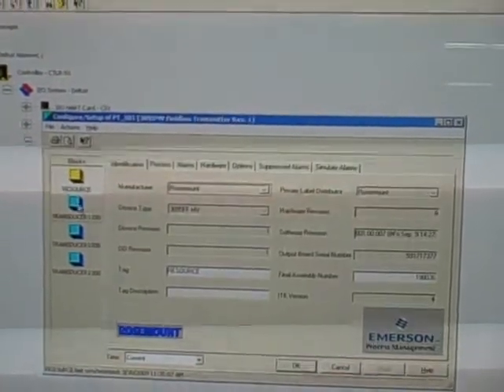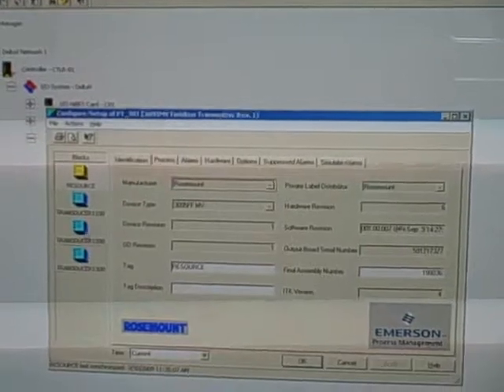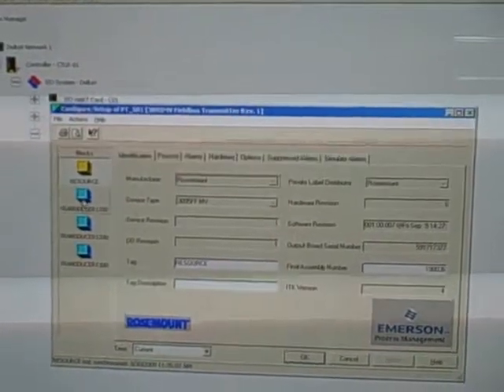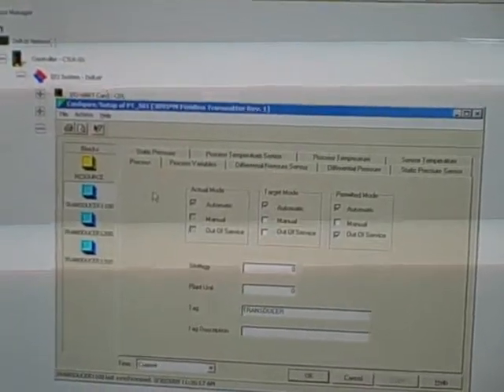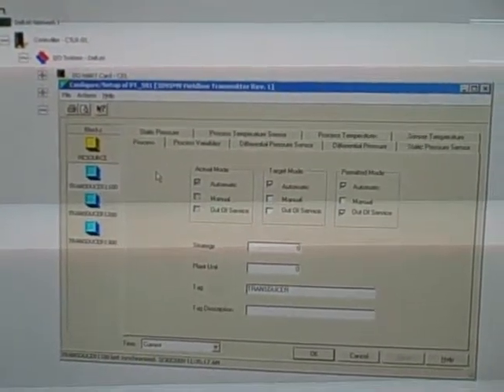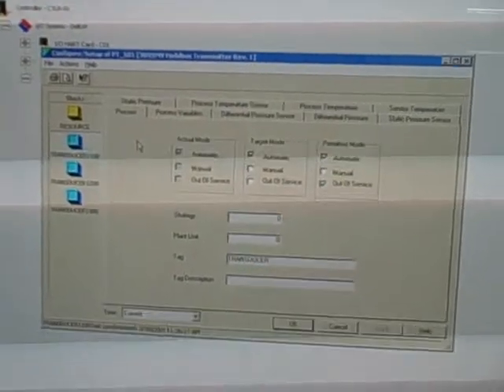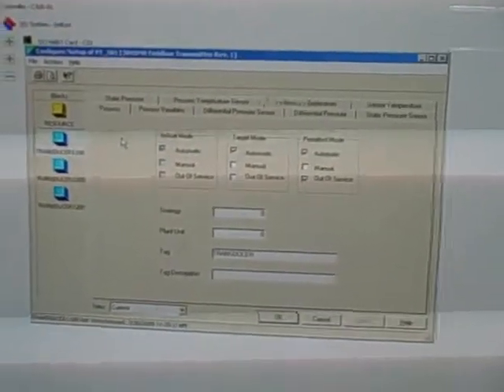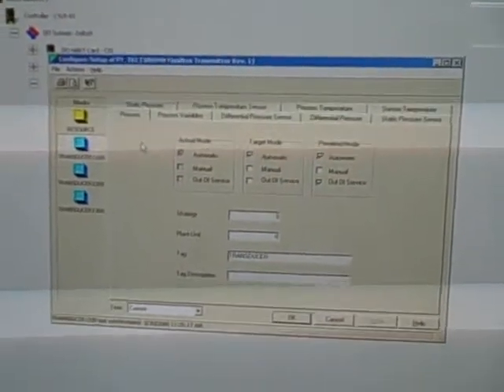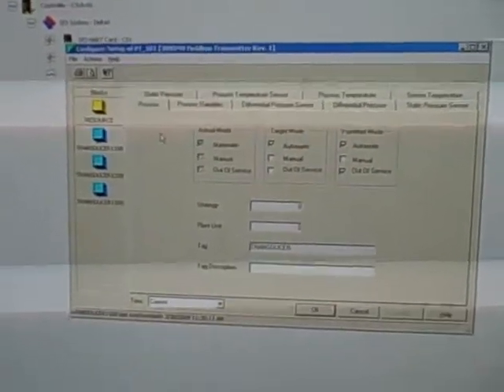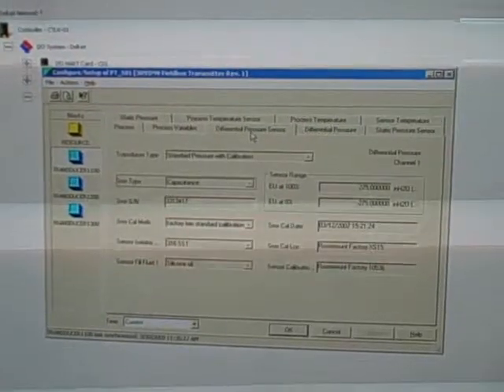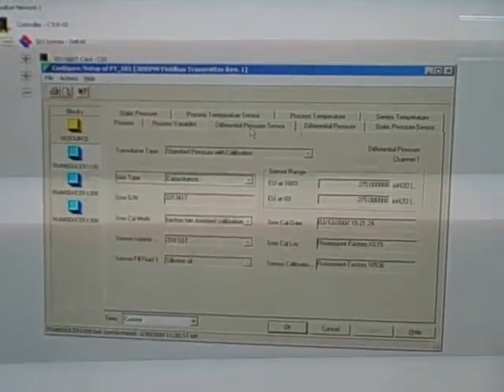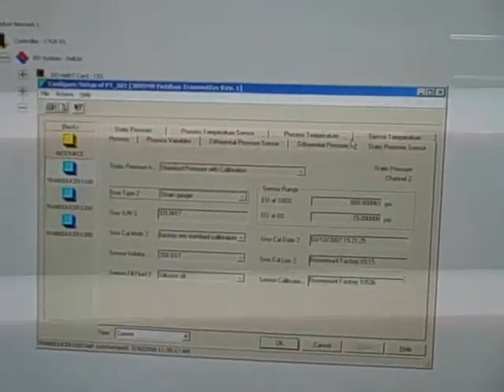It also has three transducer blocks. The first transducer block is used for interpreting the direct process variables. Now remember this is a multivariable transmitter, so it measures differential pressure, which you see right here. It also measures static pressure and process temperature.